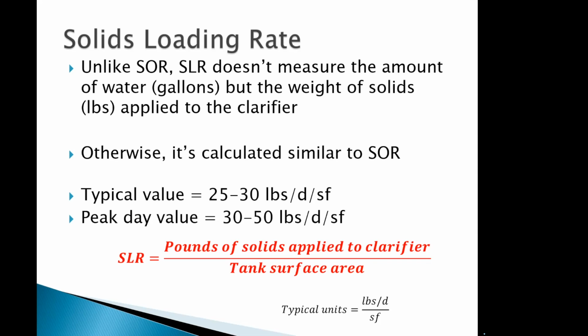Because again, there's just more solids to deal with, and we need to give them all enough time to settle to the bottom of the tank. So solids loading rate is calculated very similar to surface loading rate, except that we use the pounds of solids being sent into the tank instead of the gallons. So again, a typical value, something we want to compare to, is 25 to 30 pounds of solids per day per square foot of surface area of that clarifier.